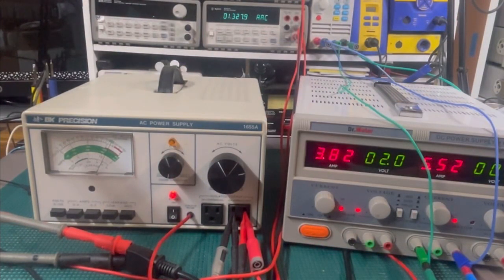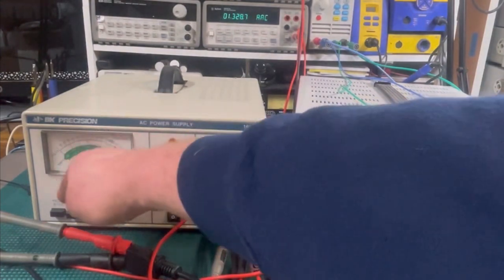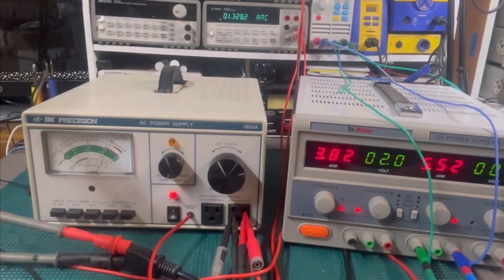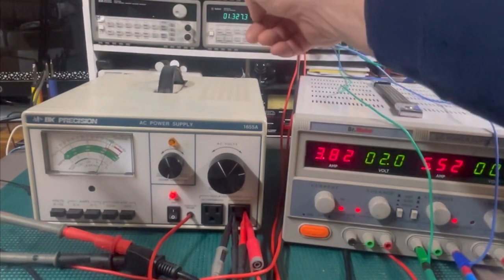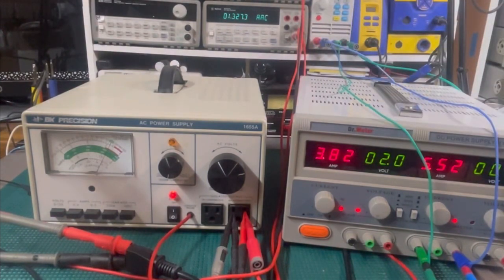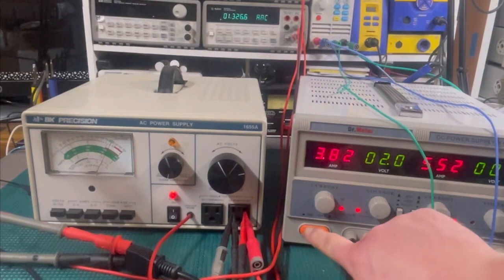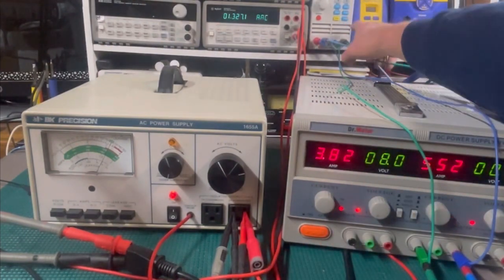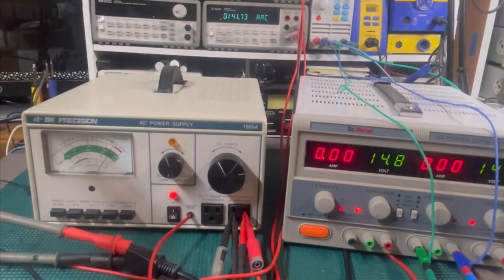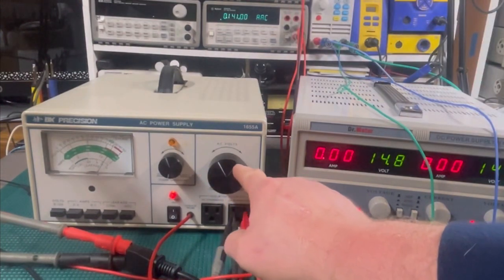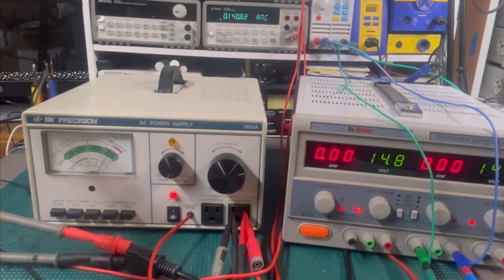Maybe there's something going on with these switches. Maybe these switches need cleaned, because now look at that. Now we're almost reading 120. Oh no, we're reading 120 bang on. And we've only got 111 coming out because there's a load on it. Let's turn this load off. Okay, we went up to 118 actual. Yeah, that makes me feel a little bit better. Maybe there's something funky going on with the contacts in these switches. I've got hope for this still.